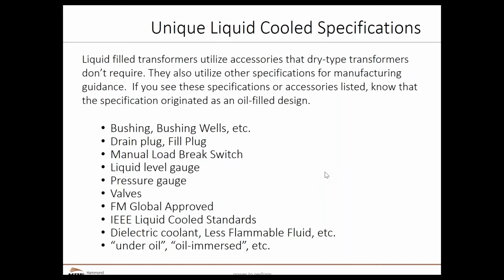Manual load break switches are, again, something that's more common within liquid filled transformers. There are certain things that I can do with a switch that's surrounded by the oil the transformer is using that I can't do as easily if it is what we call an air switch, a normal switch that operates in the air versus something that is submerged in oil. Obviously, things like liquid level gauges and pressure gauges all indicate that I'm using some type of liquid.